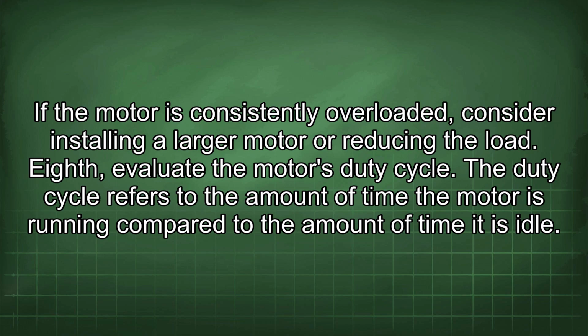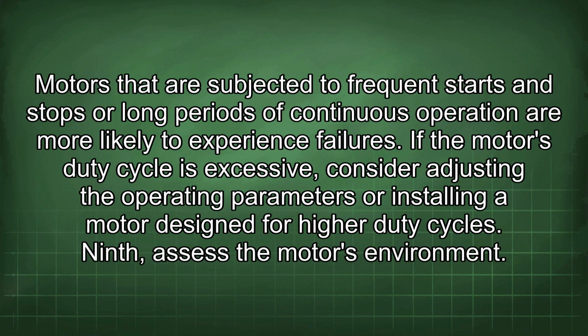Eighth, evaluate the motor's duty cycle. The duty cycle refers to the amount of time the motor is running compared to the amount of time it is idle. Motors that are subjected to frequent starts and stops or long periods of continuous operation are more likely to experience failures. If the motor's duty cycle is excessive, consider adjusting the operating parameters or installing a motor designed for high duty cycles. Ninth, assess the motor's environment.